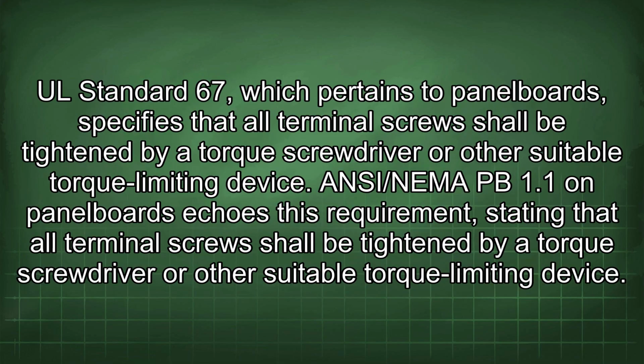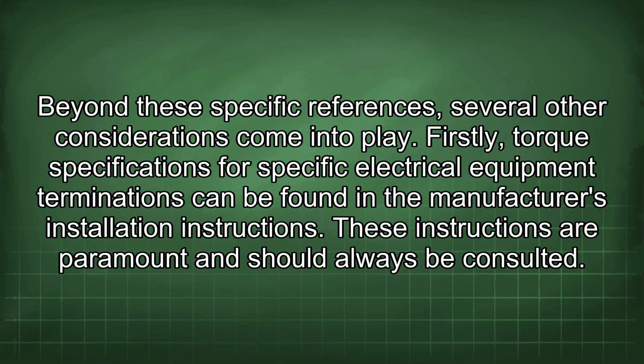UL Standard 67, which pertains to panel boards, specifies that all terminal screws shall be tightened by a torque screwdriver or other suitable torque limiting device. ANSI/NEMA PB 1.1 on Panelboards echoes this requirement, stating that all terminal screws shall be tightened by a torque screwdriver or other suitable torque limiting device. Beyond these specific references, several other considerations come into play.